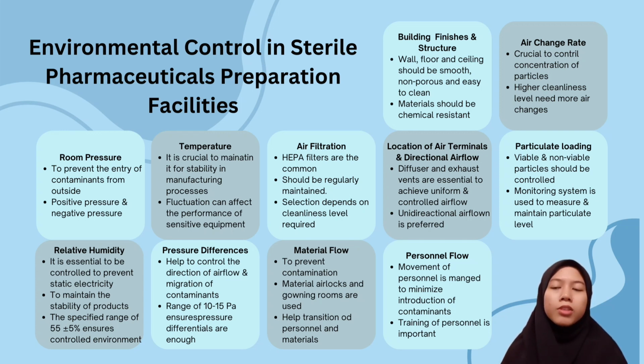Maintaining a specific temperature is crucial for stability in the manufacturing process, as temperature fluctuation can affect the performance of sensitive equipment. Then, relative humidity. Its specified range of 55 plus or minus 5% ensures a controlled environment that minimizes the risk of electrostatic discharge and other humidity-related issues. Next, pressure differential. The specified range of 10 to 15 Pascal ensures that the pressure differentials are sufficient to maintain the desired airflow patterns without causing discomfort to occupants.